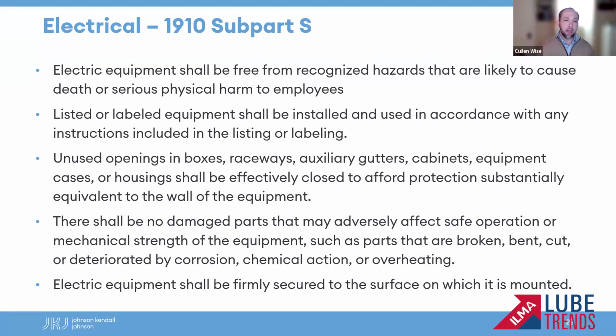The issue is that box, the knockouts could be pushed into the box. If somebody were to grab the box, their finger could go into the box and then be exposed to the live electrical. So that's not the intended use of that equipment, and that's something that would not meet the listing or the labeling. It's just a simple example. There's plenty of other ones.